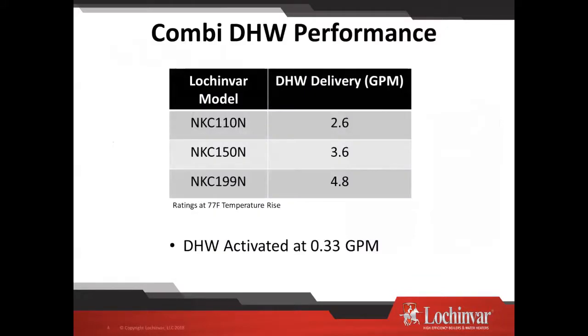Important little feature to know right here is the domestic hot water delivery capacity of your unit. 2.6 gallons a minute. Now that on a 110, that's considered at a 77-degree rise. So just keep that in mind. If you have really cold groundwater, that might not get you to that 120-degree water you're looking for. But 2.6, 3.6, 4.8, those are some things.